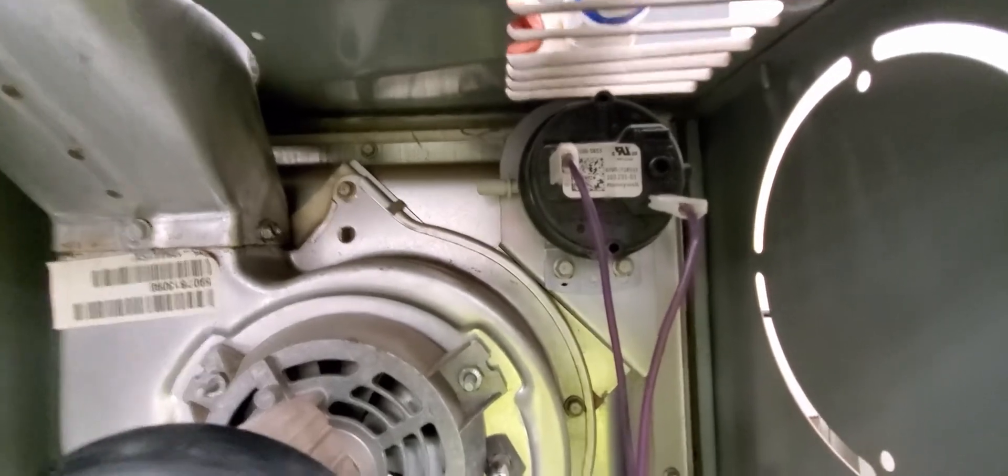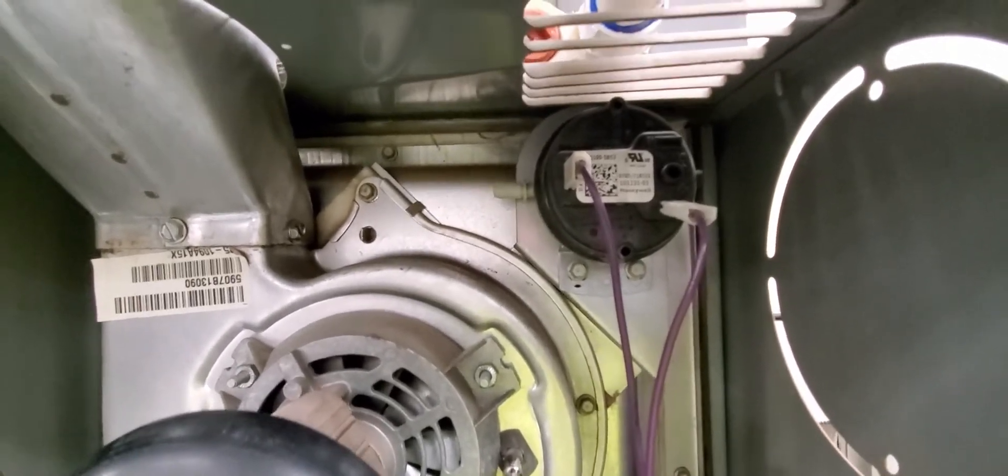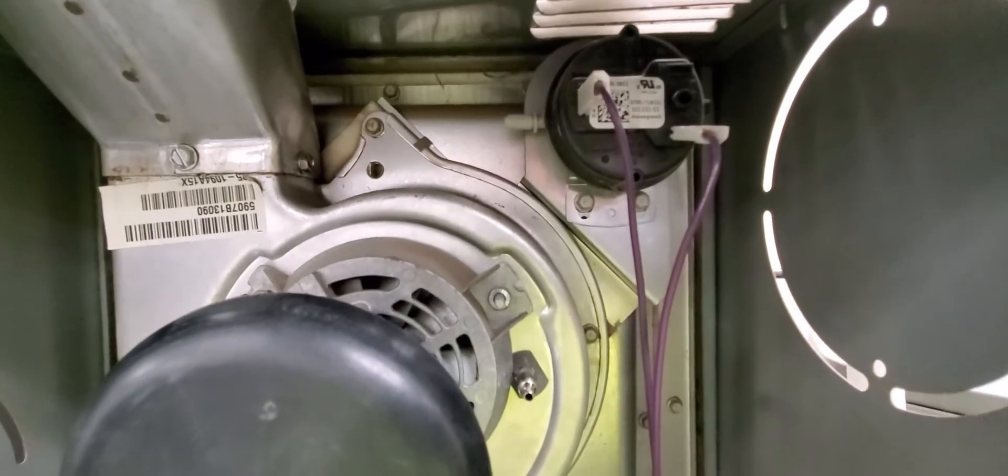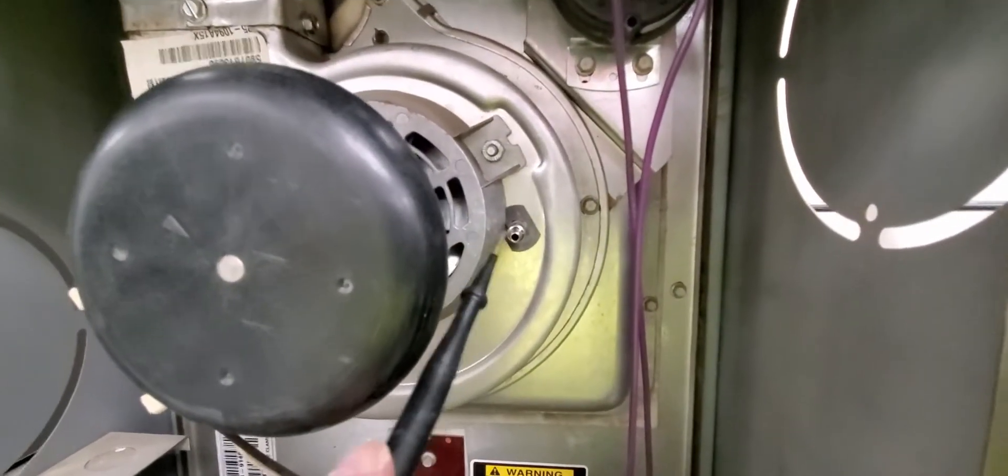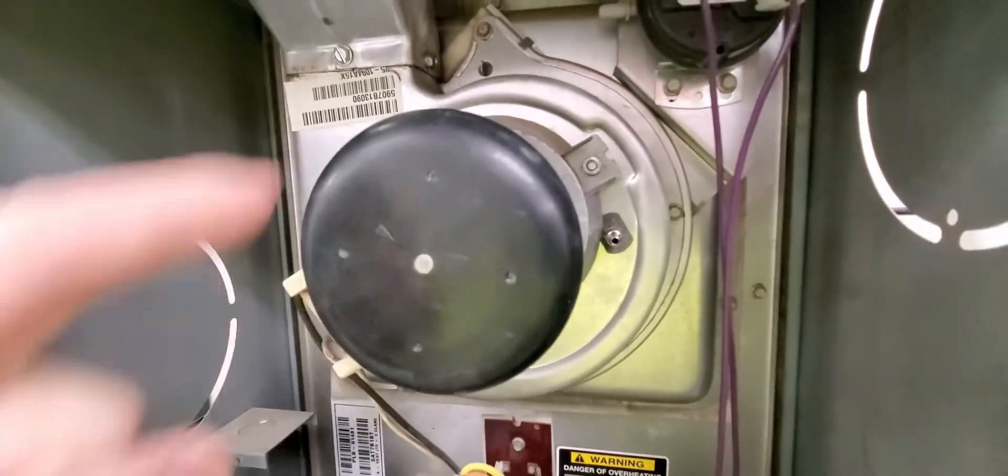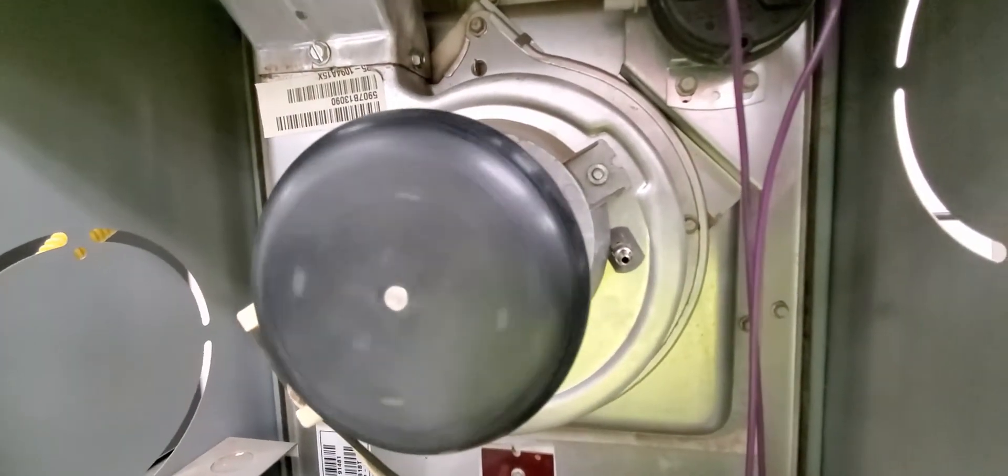That's what this one's rated for. I would hook up my manometer to it when it's running to see that I'm getting 0.4 out of the motor itself. Make sure that it's venting and everything's not making any noise.